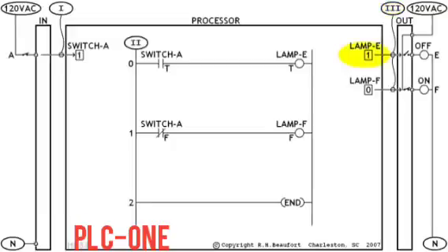There's a 1 in the bit, so the processor goes to the module and gives it a signal to turn the output on. There's a 0 in this bit, so the processor goes to the module and gives it a signal to turn the output off. And we're through with this scan cycle. And unless something changes, that same sequence gets repeated several hundred times each second.